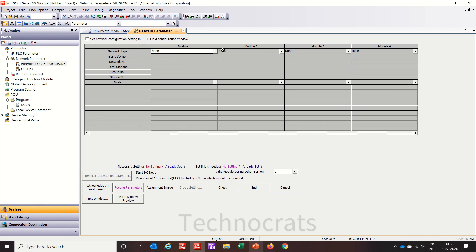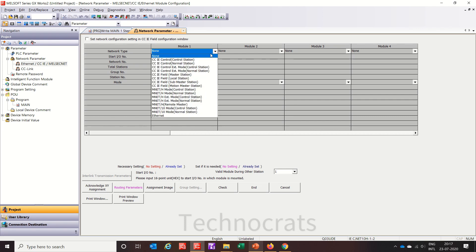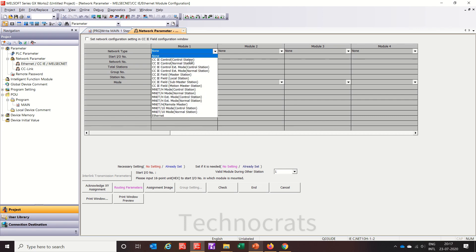Module 1 I will use as control master — this is the master station. The starting IO number is 0, the network station number is 1. We are using a total of 2 stations here, which includes one slave. Group number and station number is 1.